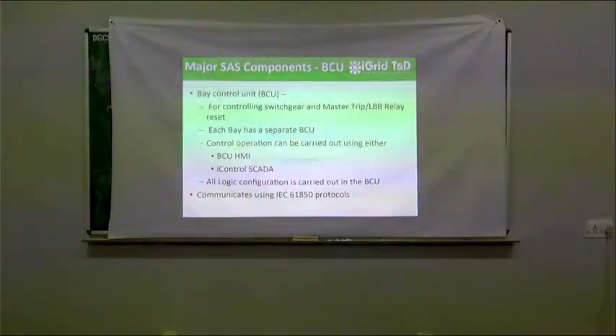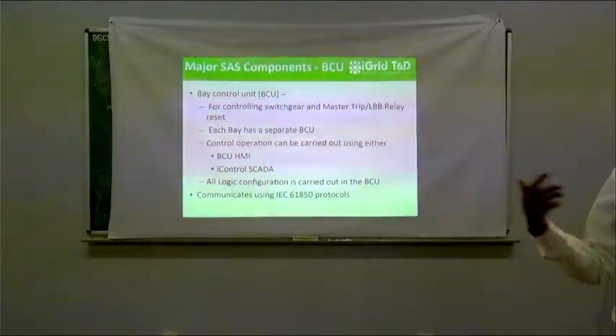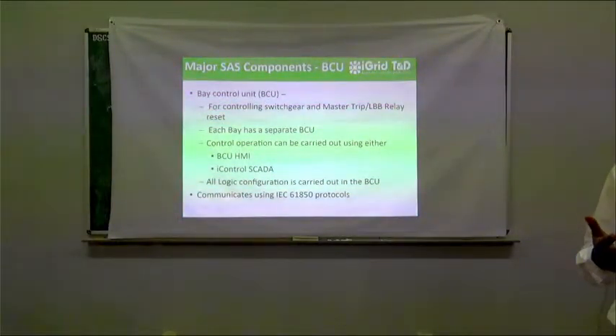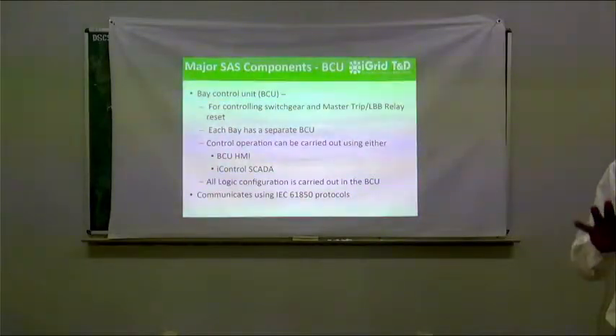The main thing is that all these BCUs communicate on the IEC 61850 protocol. What is the IEC 61850 protocol? It is a protocol which has been standardized for substation automation across the world. In India, whenever we do any substation automation, we always specify IEC 61850. What are the advantages of 61850? I will take it up in the coming slides. Basically, the advantage is that it can support multi-vendor equipment. There is a standard set of objects and classes which has been defined, and every vendor has to be compliant with that. Only then can it communicate.